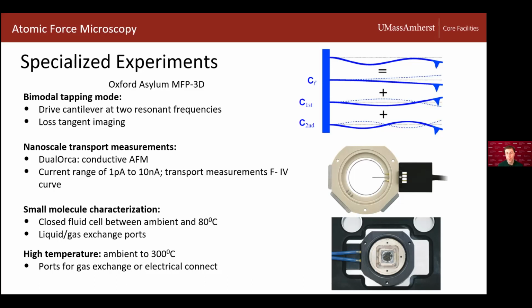Earlier we talked about tapping mode, in which we're driving the cantilever at its fundamental resonance frequency. Well, in this bimodal tapping mode, we're able to simultaneously oscillate the cantilever at a higher eigenmode, a frequency higher than its fundamental. So we have essentially two resonant frequencies that the cantilever is being driven at here. Some interesting results can come from this, things like loss tangent imaging. Also, we have the capability to look at nanoscale transport measurements.